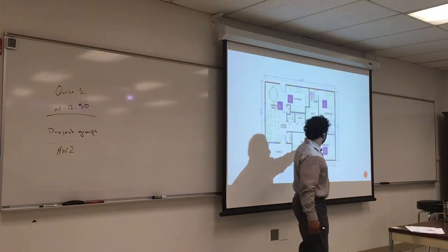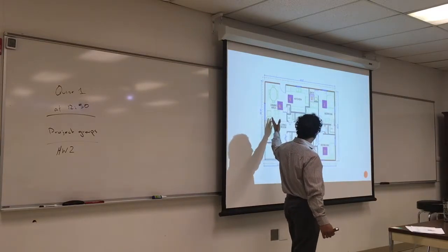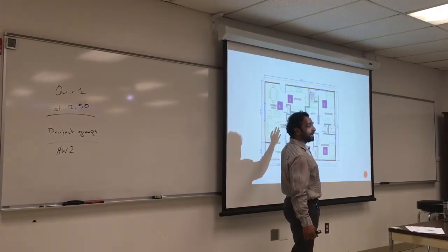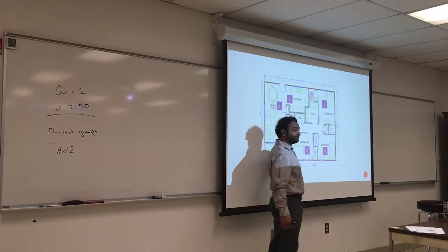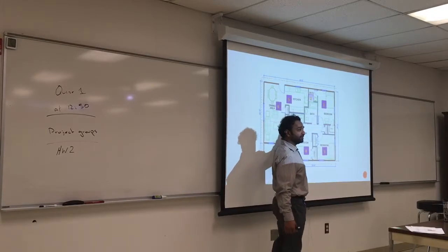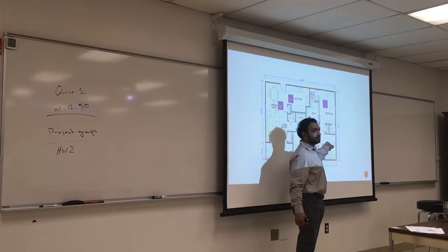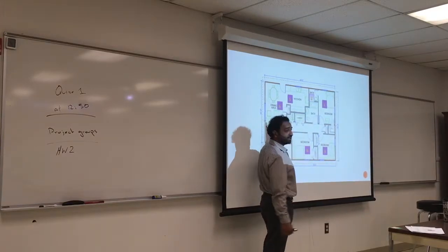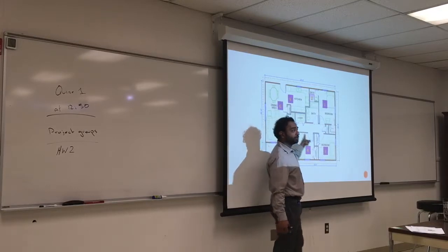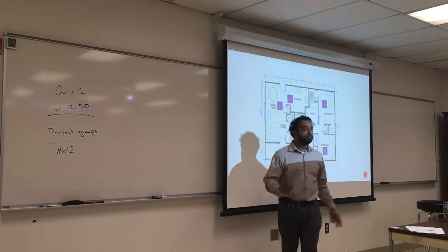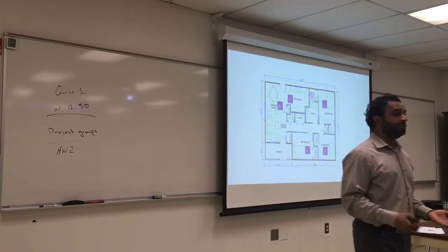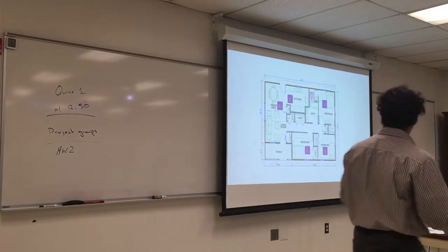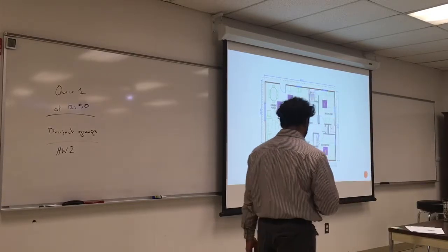But at least one area will be warmer at night than the dining area. And if you have one thermostat, you're going to have uneven heating. You put the thermostat here, I see that's 65. What is the temperature here? It might be 80. You might get it too hot in here, and this will be very cold. So make sure you have two zones at least in a house, with the sleeping area having its own thermostat, and the living area having its own thermostat.